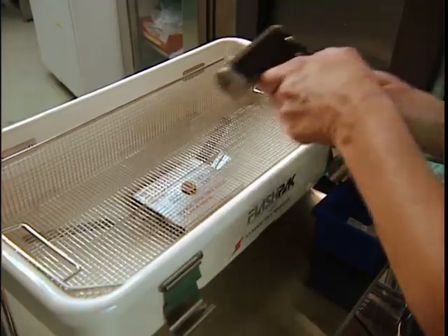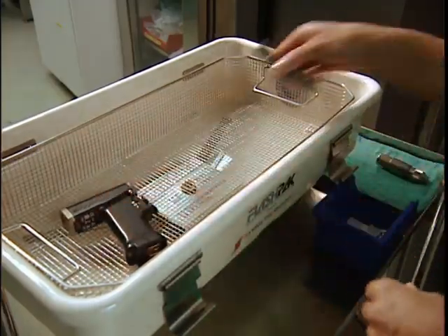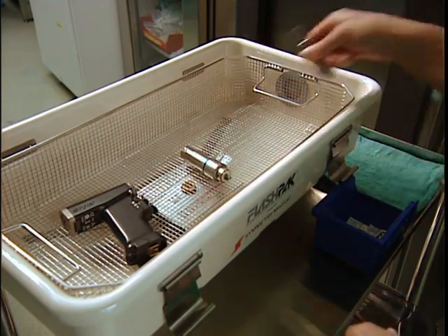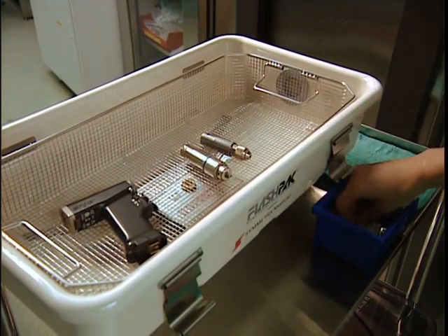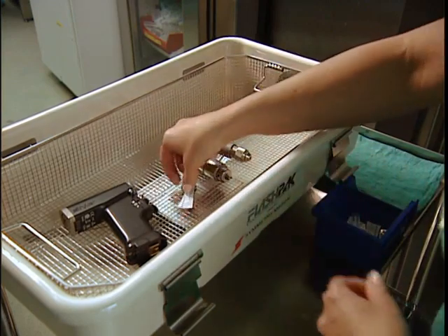Most of us that work in healthcare are familiar with the term flash sterilization. It's been around for a very long time, and it was used to denote an emergency situation where unwrapped instruments were placed into the sterilizer on a standard cycle with a very short dry time in order to turn the instruments and get them quickly back to the operating room. The term flash sterilization is no longer used and has been replaced with the term immediate use steam sterilization.